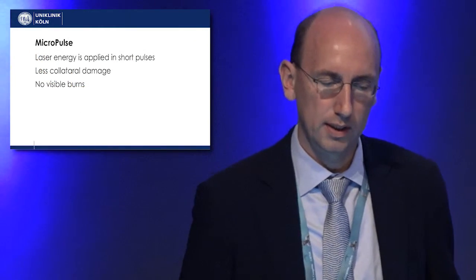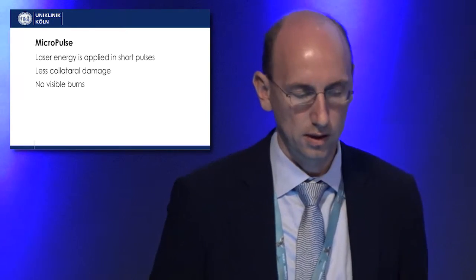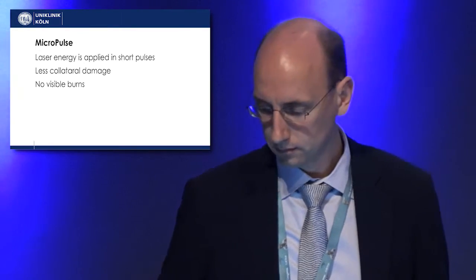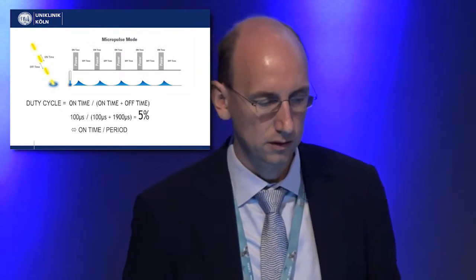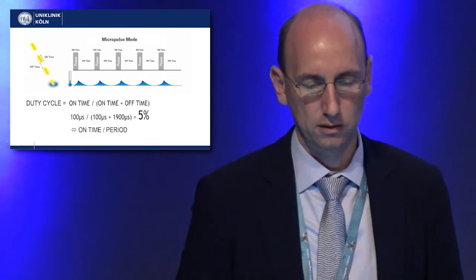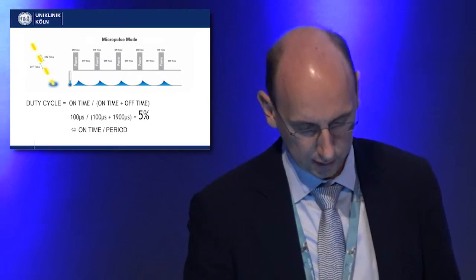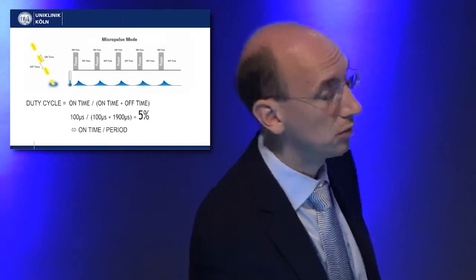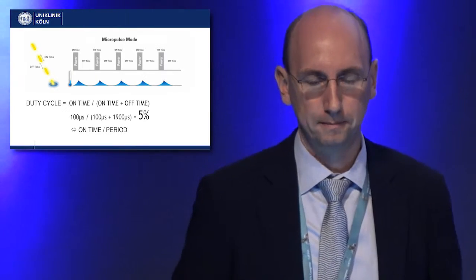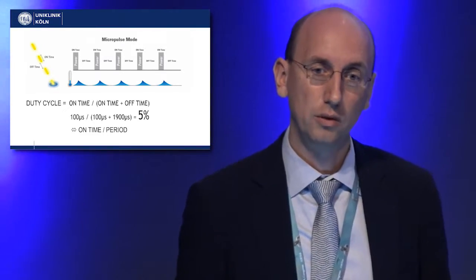With MicroPulse, you apply the laser energy in short pulses, so there is no real heat buildup and no visible burns. The laser beam is cut into small pieces — the laser is on briefly, then there is a long off-time where the tissue has enough time to dissipate all the heat, so you don't build up any heat and you create no scar.